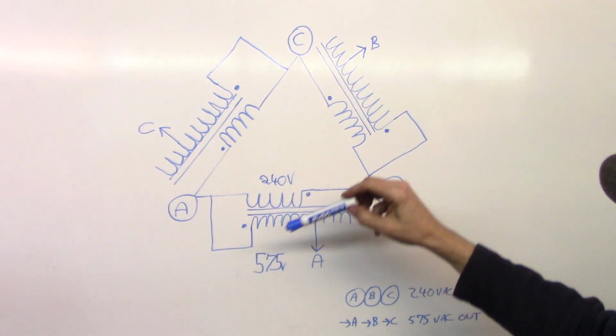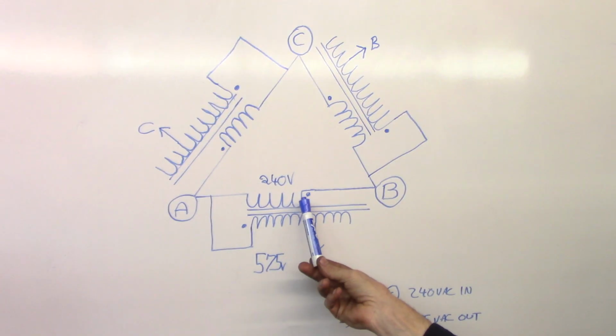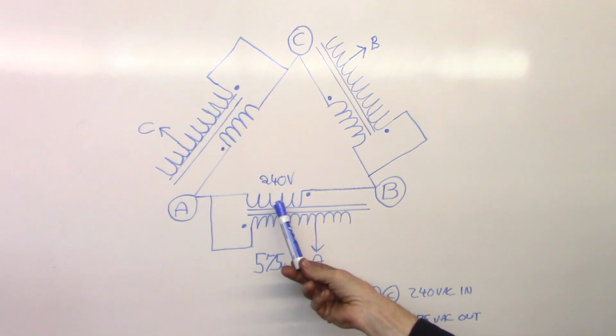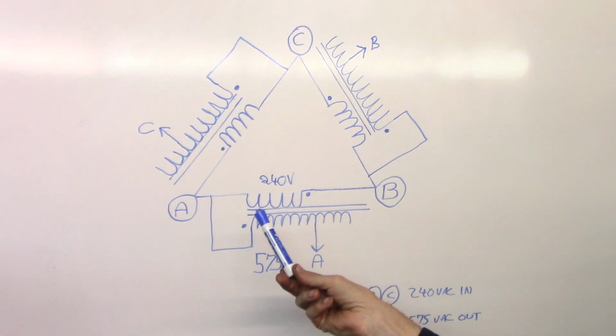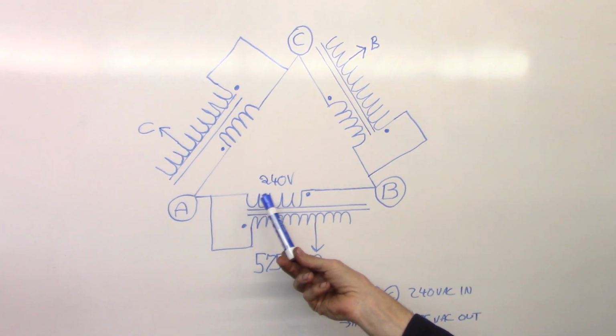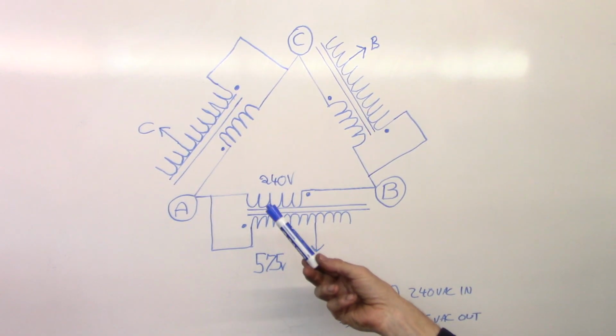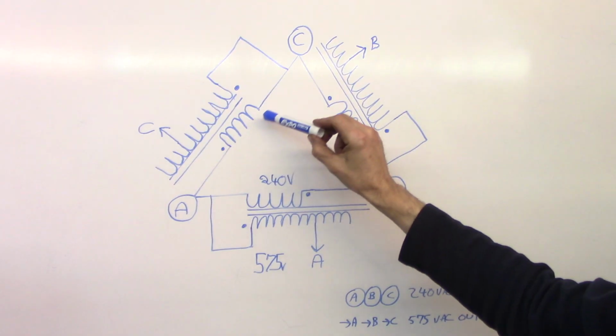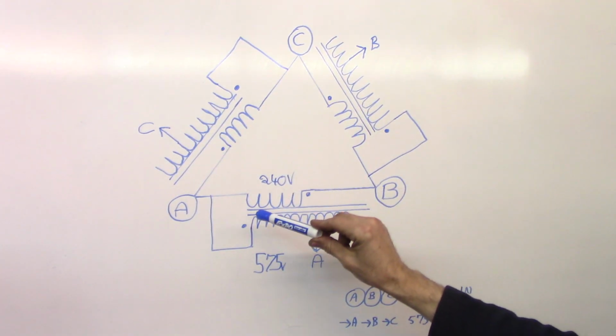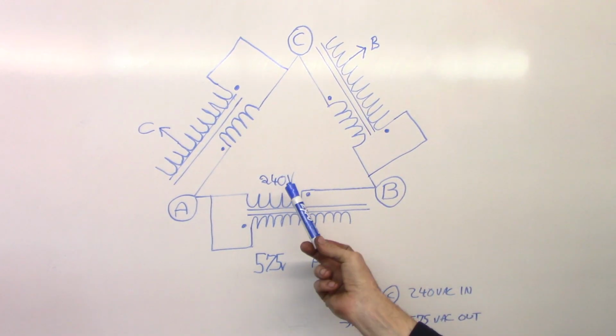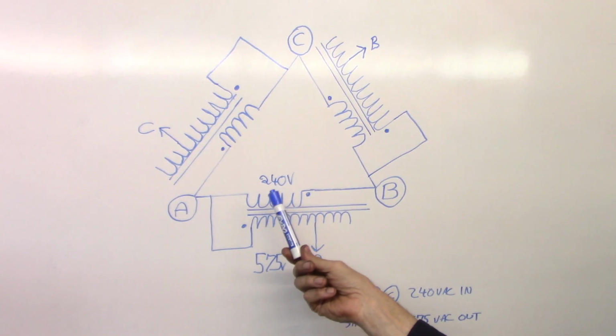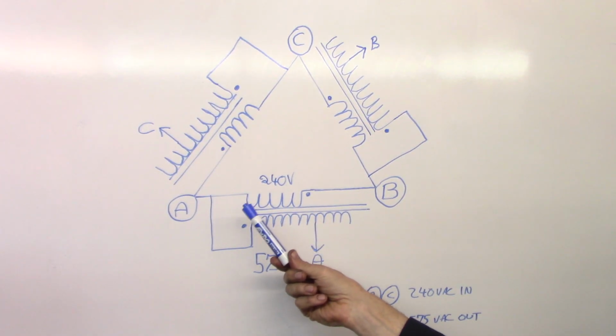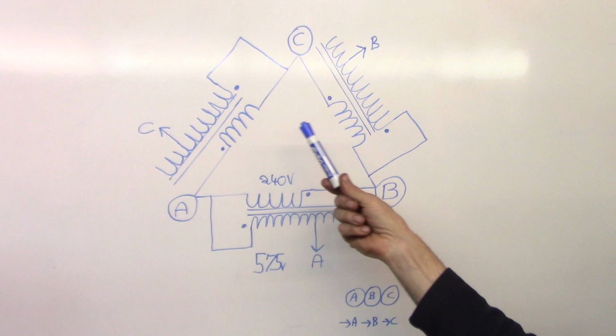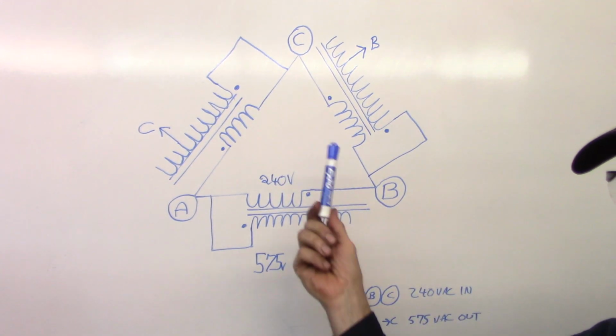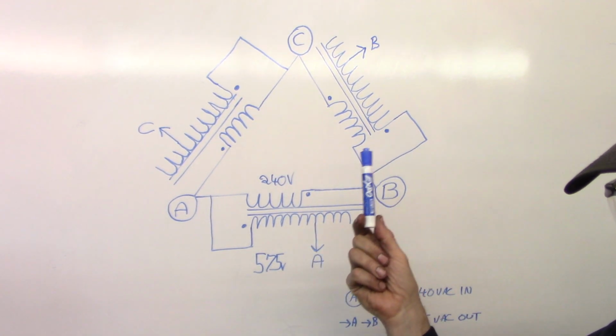So only pay attention for now - I'm powering up 3 coils, 3 transformers. The primary, 1, 2, and 3. So all these transformers - it's actually the secondary coil, but the coil that's supposed to be 240 volts is 240 volts on all of these guys.